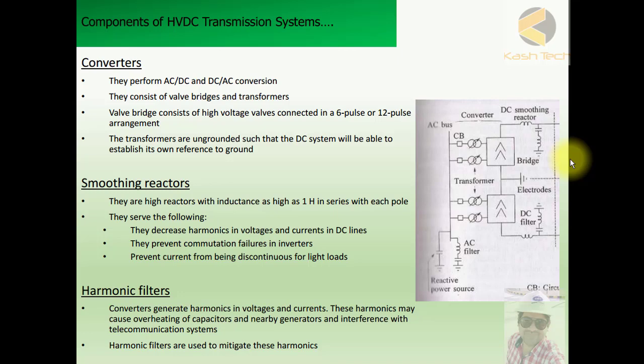Converters consist of valve bridges and transformers. The valve bridge consists of high voltage valves connected in 6-pulse and 12-pulse arrangements — these are the thyristor gates and valves used for conversion. The transformers are ungrounded so that the DC system is able to establish its own reference to ground.